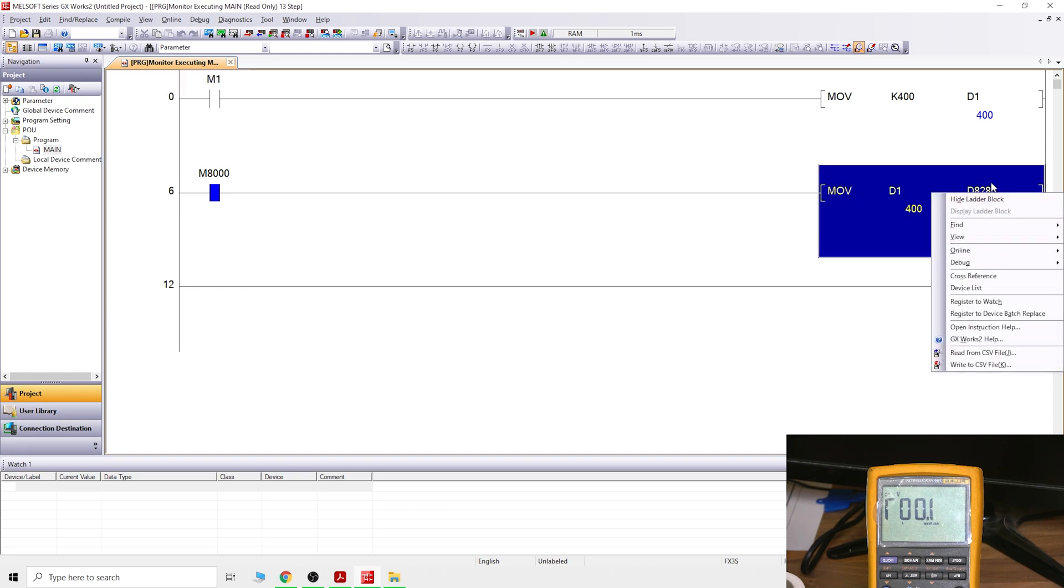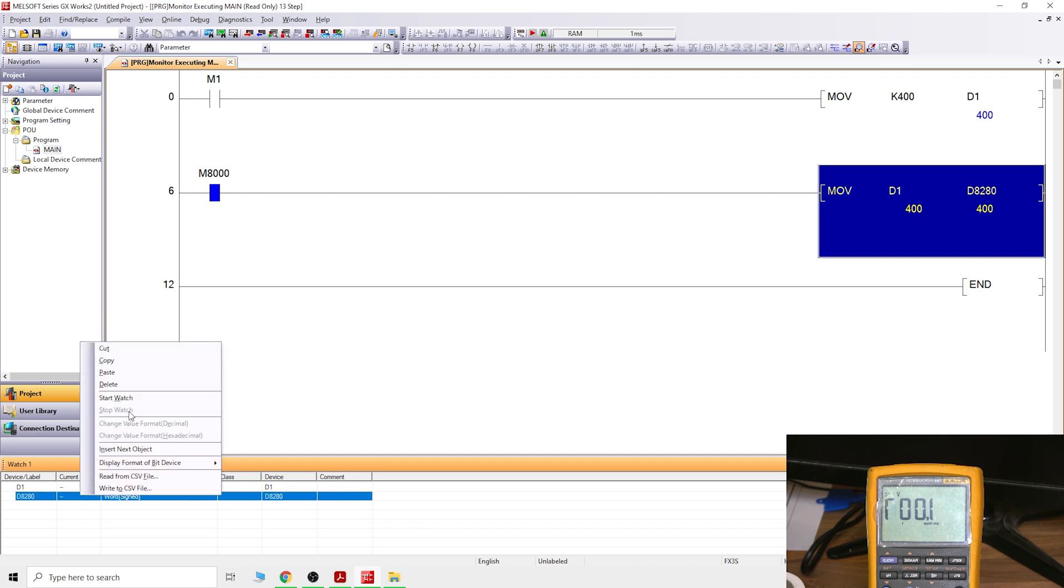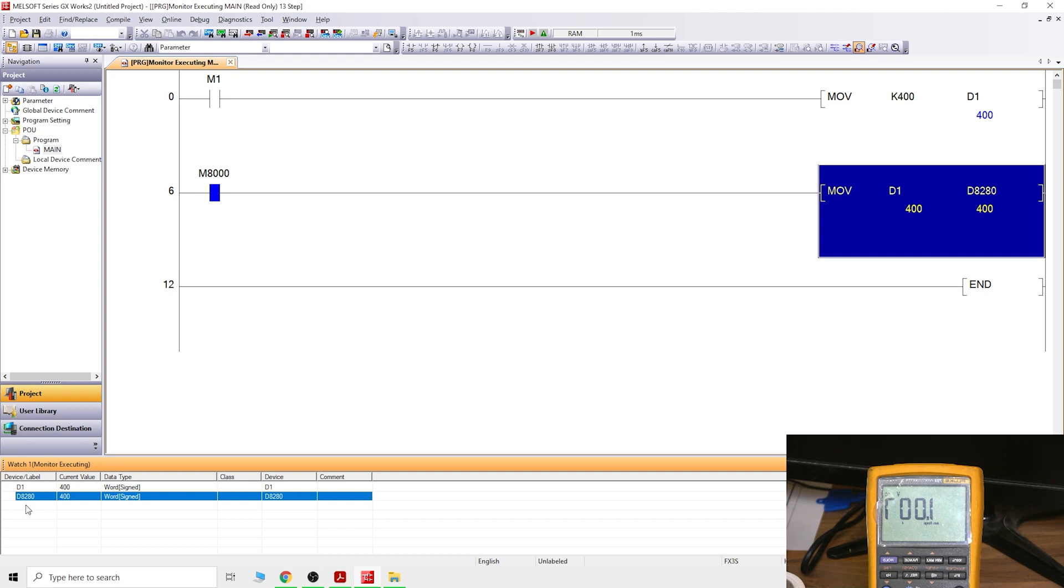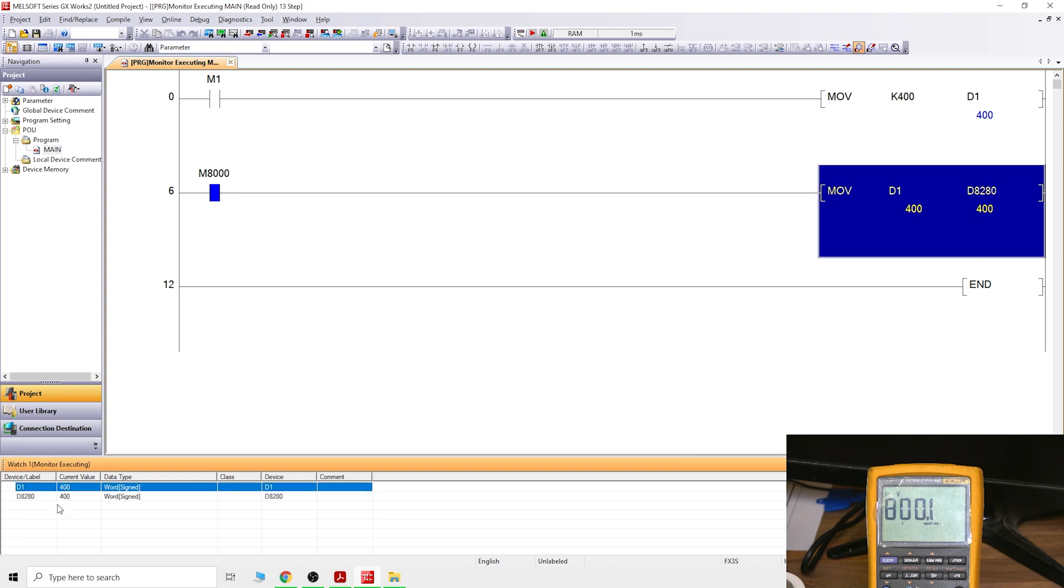If you want to check it out, what else is happening there, you can go to the register to watch. You see both values have come up, you can start to watch. Those values are there, but you cannot edit the D8280 because that is read only. If you try, let's say 800, nothing will happen because it's not meant to happen. You cannot just edit those values in that data register.